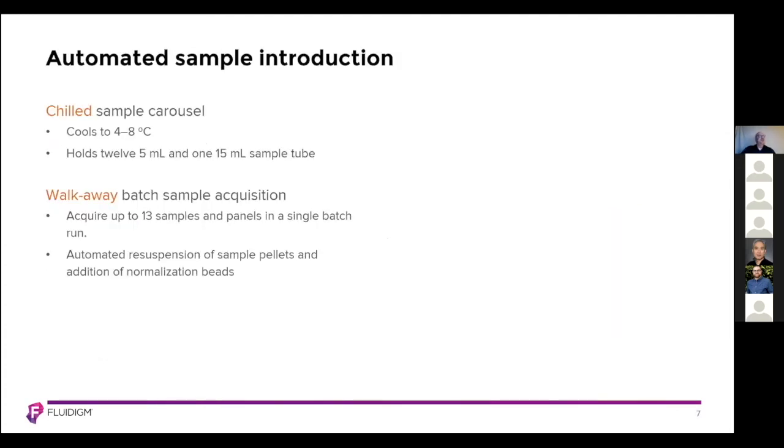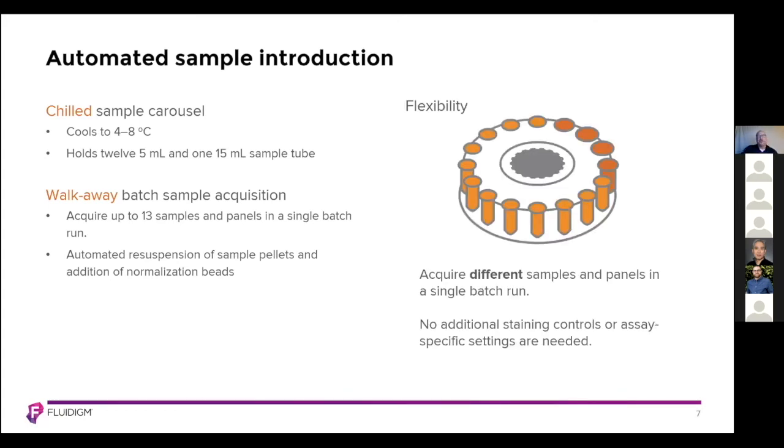We have automated sample introduction with a chilled sample carousel for walk-away batch sample acquisition. Our carousel is cooled to 4 to 8 degrees Celsius and holds up to 12 five-milliliter tubes and one single 15 ml tube. The walk-away acquisition is unique to CyTOF in our latest version — it is able to acquire up to 13 samples and 13 individual panels in a single batch run. Automated resuspension of sample pellets and the addition of normalization beads is also a key feature, affording one operator or core director the flexibility to acquire different samples with different panels in the same batch run. No additional staining controls or assay-specific settings are needed even with 13 individual panels loaded.